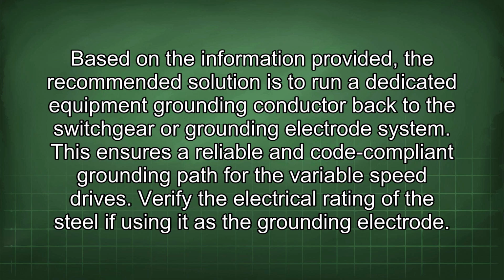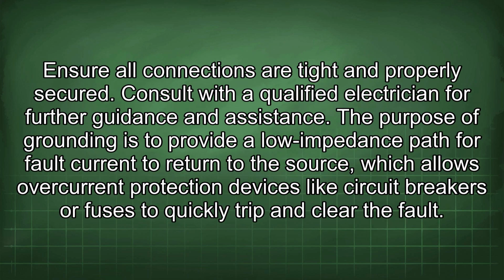Verify the electrical rating of the steel if using it as the grounding electrode. Ensure all connections are tight and properly secured. Consult with a qualified electrician for further guidance and assistance. The purpose of grounding is to provide a low impedance path for fault current to return to the source, which allows overcurrent protection devices like circuit breakers or fuses to quickly trip and clear the fault.